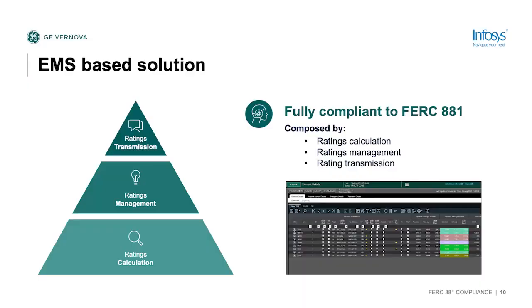So our EMS-based solution essentially is going to take your rating sets. So your rating calculations, those can come from field-based dynamic line rating sensors or GE's digital dynamic line rating sensors. Dragan will be talking about that in a little bit. It can have an ambient adjusted rating set table or a polynomial equation to define your ambient adjusted ratings. Your traditional seasonal based ratings are like a fallback method, and we'll get into that later in a demo, and then your nominal ratings.